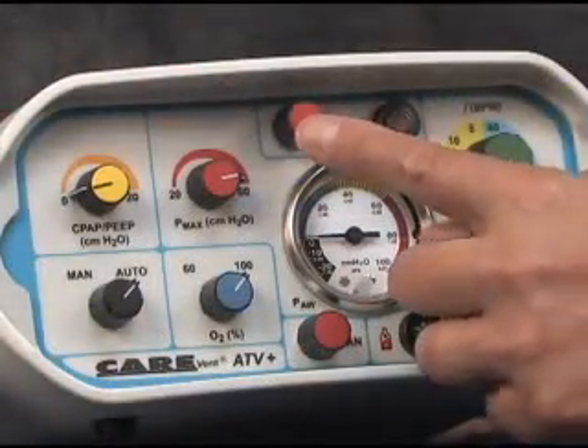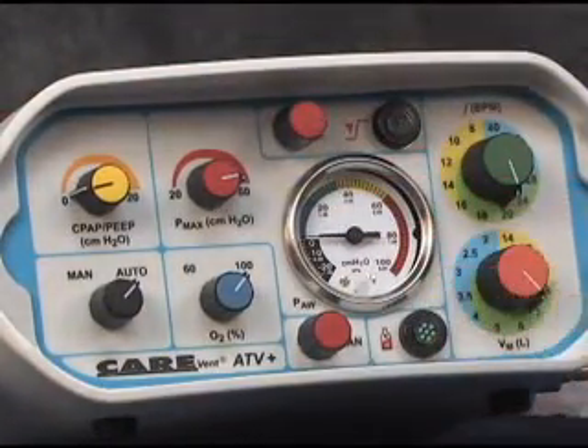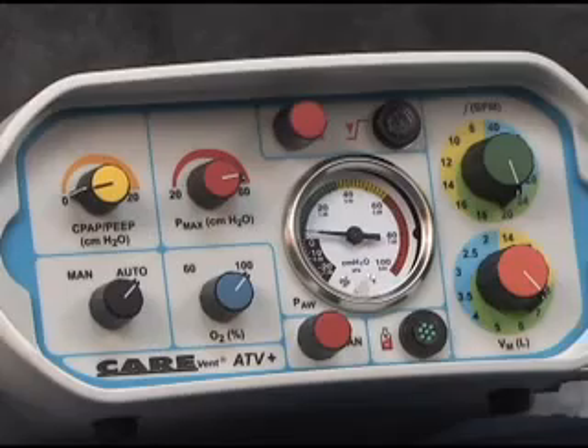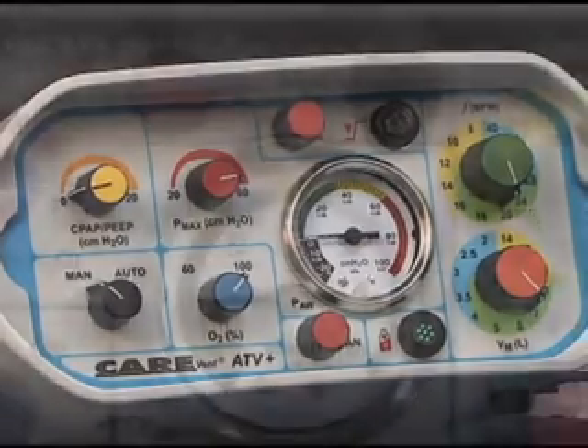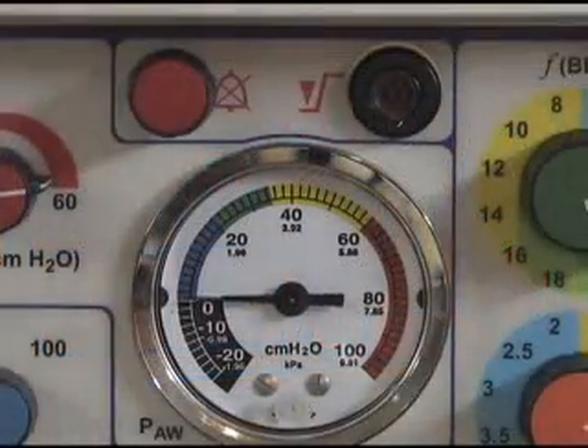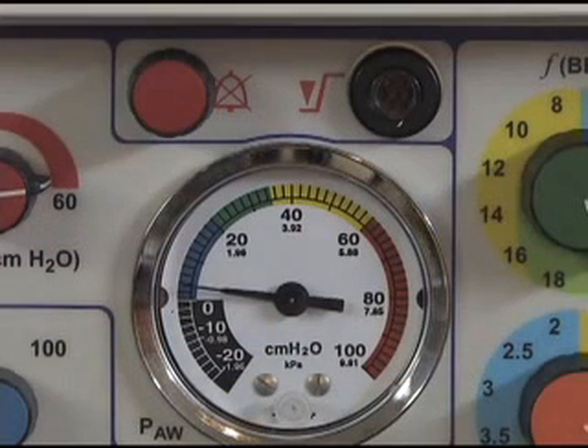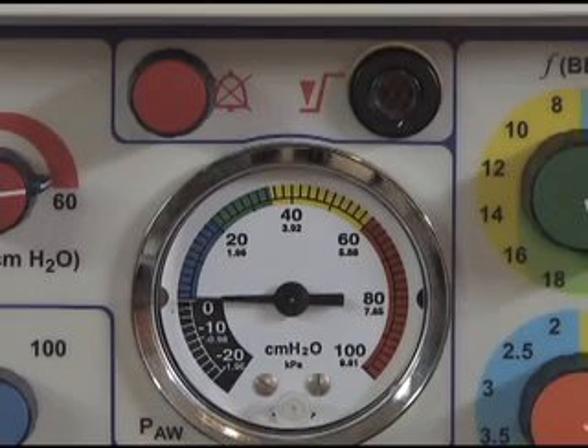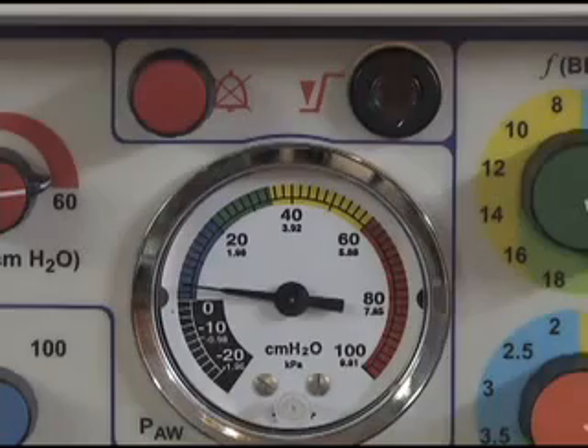Next to the visual indicator is a BSI alarm silence button that allows the operator to silence the alarm for 15 seconds when disconnection has been purposely performed for suctioning or other airway maneuver. After the delay period, the alarm will restart automatically. Each depression of the BSI alarm silence button will silence the alarm for a period of 15 seconds. If the problem is not corrected within 15 seconds, the alarm will recommence.